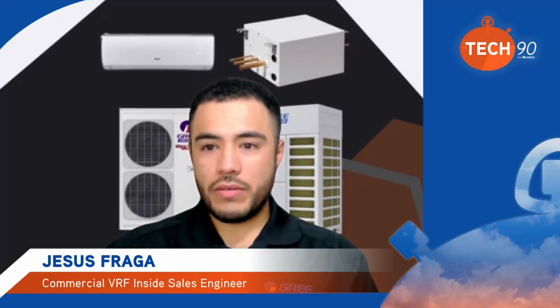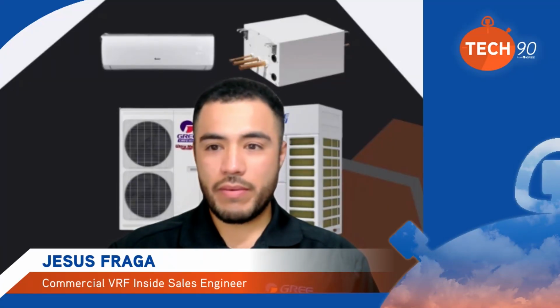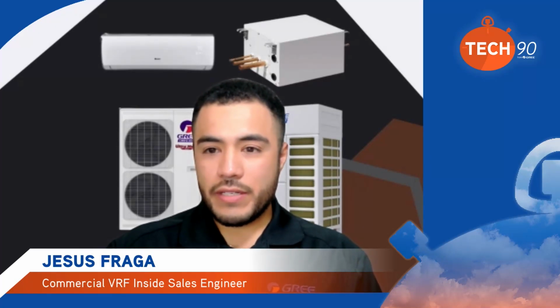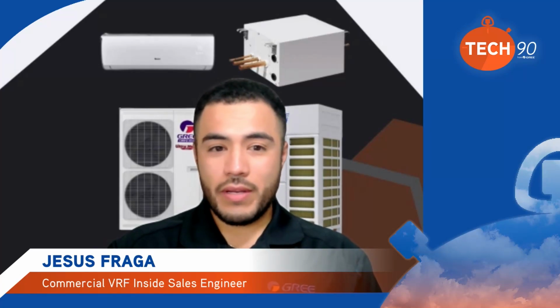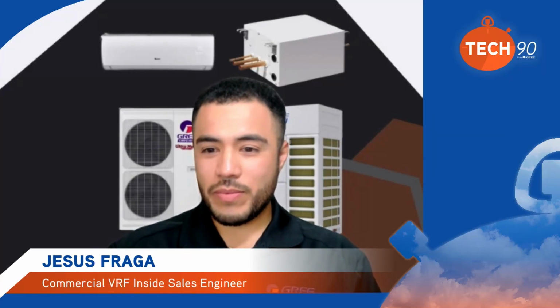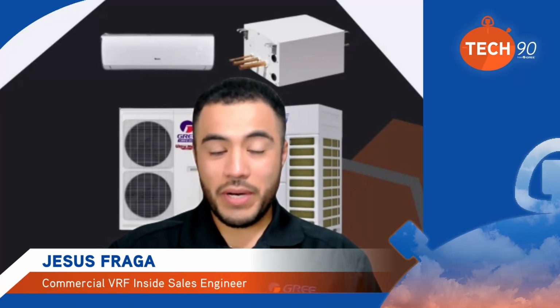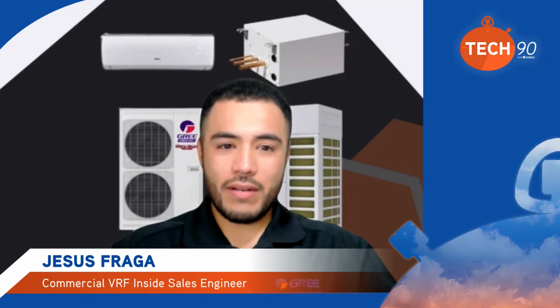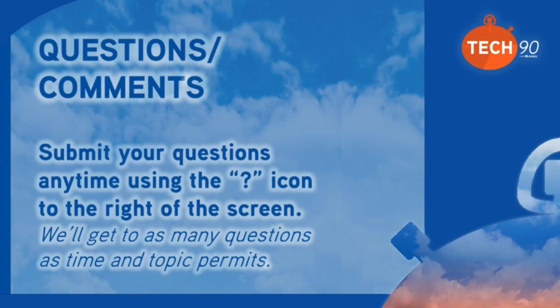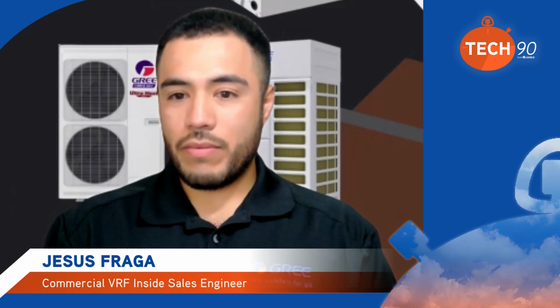Yeah, regarding the R32, as Greg stated, it's been around for 10, 15 years overseas, and the originators of that refrigerant are an actual manufacturer, which is obviously our competitor. What I'm getting at is, it's not a refrigerant that was developed by, for instance, a chemical company. It was an actual manufacturer that developed it. They've since released that patent, so it gives you a little more comfort knowing an actual manufacturer made this, tested it in their systems, and also used it in their systems. So it's just something to double down on regarding R32 and its presence in the field now and in the past. Yep.